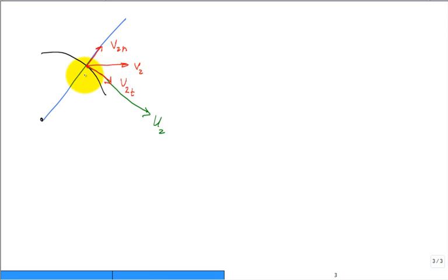Our blade is curved, and I'm going to show a backward curved blade right here. At that point right here, this is the inlet eye. You could do the same thing, but what we're going to do is extrapolate this curvature, straight line back, and this is an angle beta. This is an angle beta 2 because it's the angle going out at exit 2.